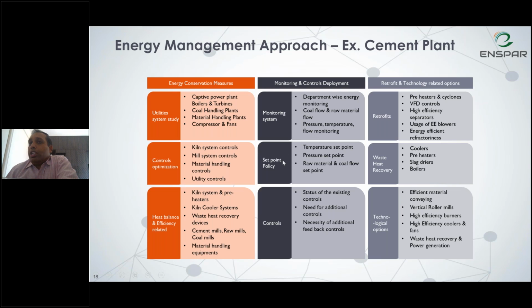The other aspect is on a set point policy perspective: what are the temperature set points, what are the coal flow set points, what happens if it goes above or below this set point, how are we going to monitor the minimum maximum conditions, and what happens if it goes beyond a particular set point. Those kinds of things need to be evaluated. The last one is on the controls aspect, like what controls need to be done to move that particular parameter within range, and that is where a lot of automation is required.